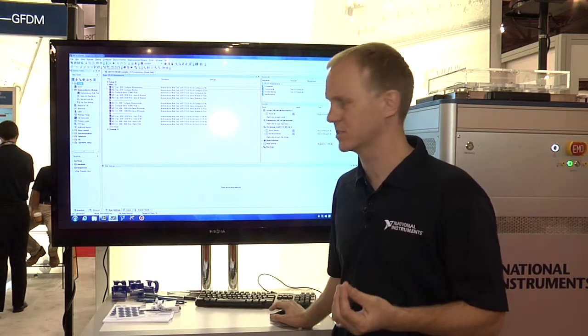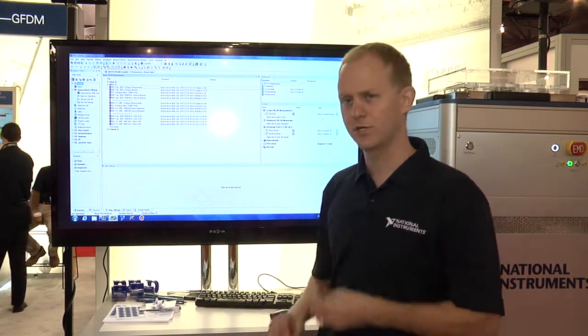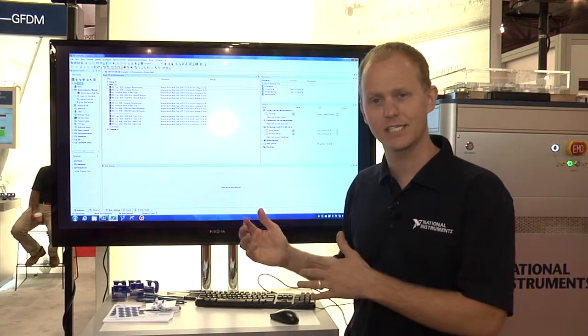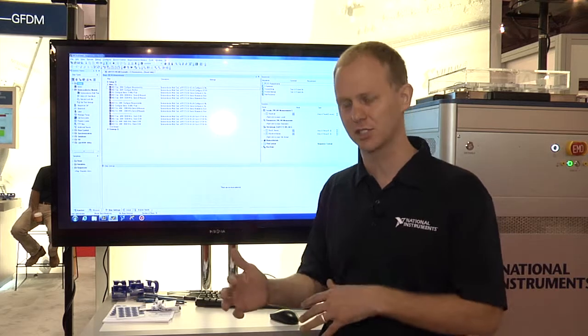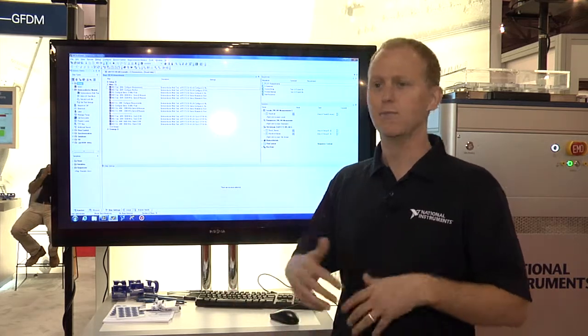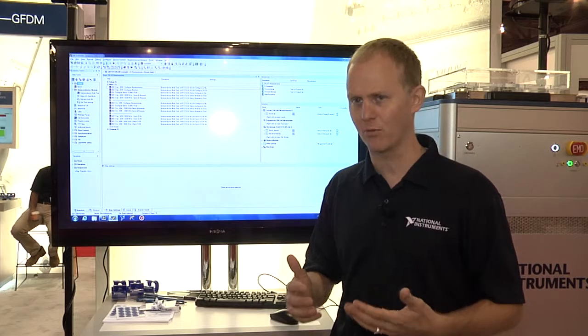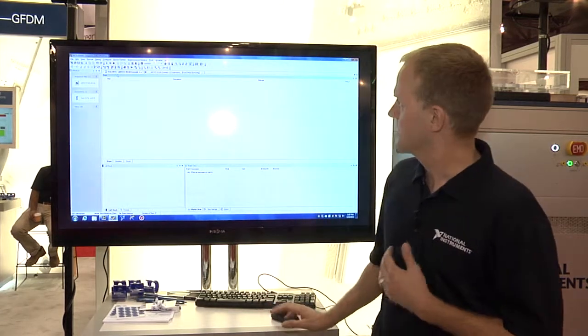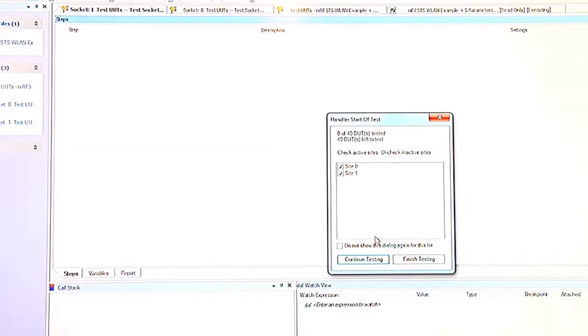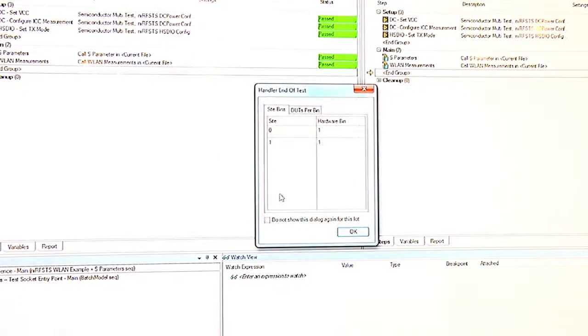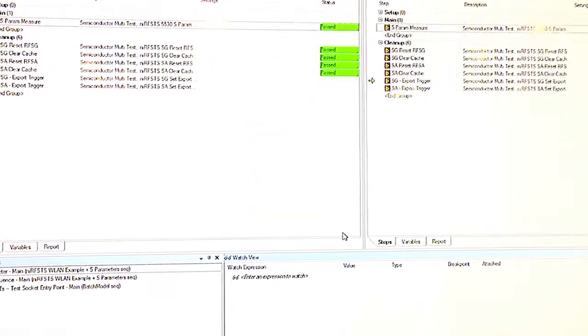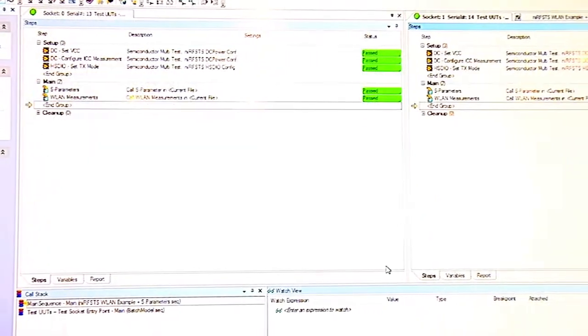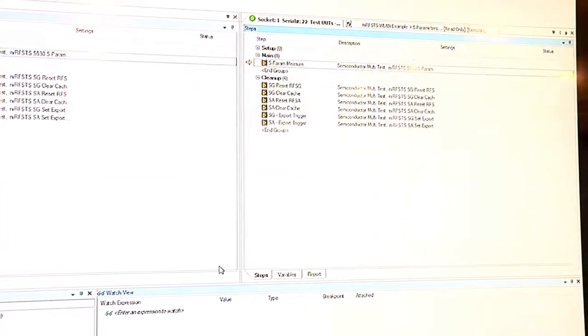One of the nice things in TestStand is that we're using the semiconductor test module plug-in, so we can program relative to the device pin rather than the instrument channel. It also has multi-site abstraction and standard test data format, or STDF, reporting. TestStand will spawn two threads to test each of our two devices in parallel, and I can add breakpoints and debug each code module in real time.